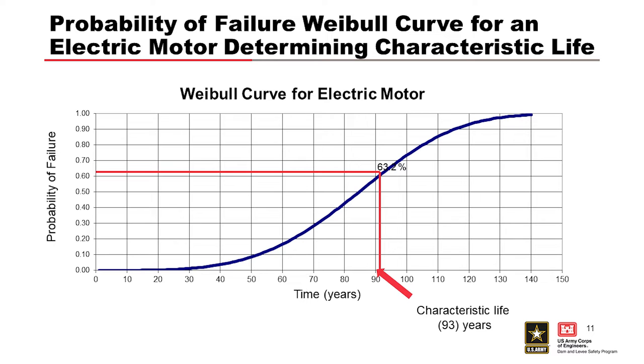Here you see a typical Weibull curve, which has been generated from data that was collected from dams throughout the core inventory. It's calculated using the Weibull formula and plotted. You can see where the characteristic life is determined, where the line meets 63.2%. And at that point, it will be 93 years old. And this particular curve is for an electric motor.